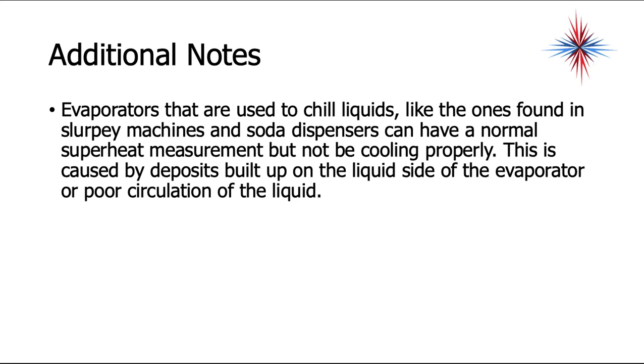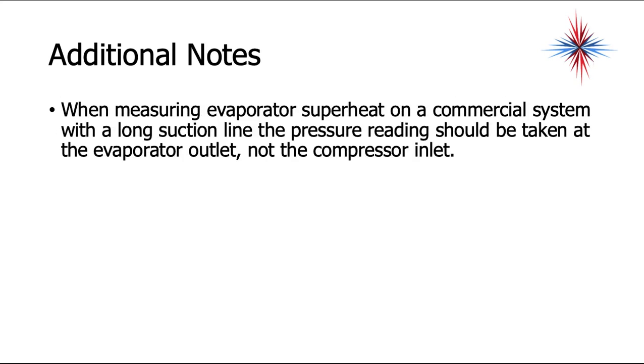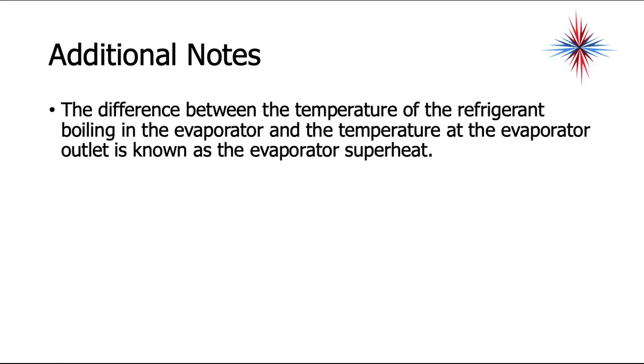System superheat is an additional measurement you'll come across occasionally. It is the difference between the refrigerant boiling temperature in the evaporator and the temperature of the suction line at the condenser, right before it goes into the compressor — taking the entire length of the suction line into account. This is actually what you're most often going to use when doing inspections and checks on split systems and package units.